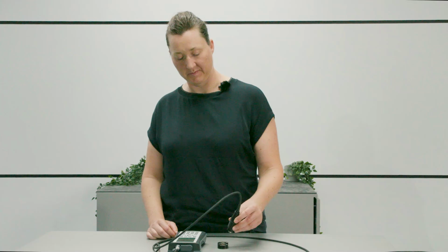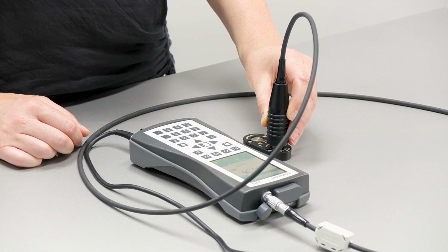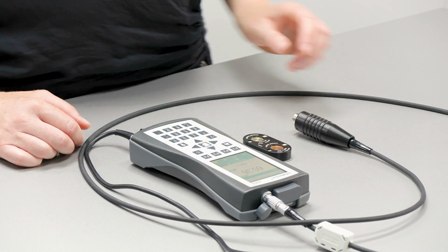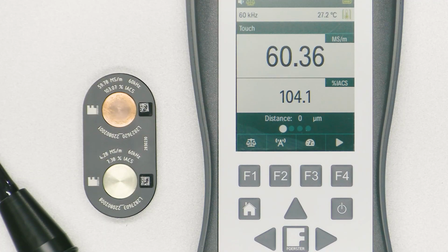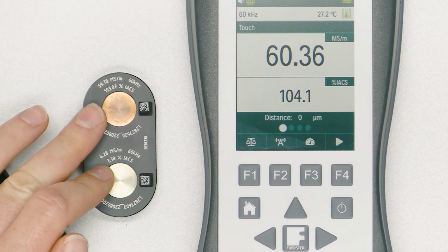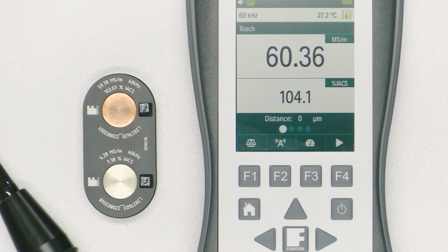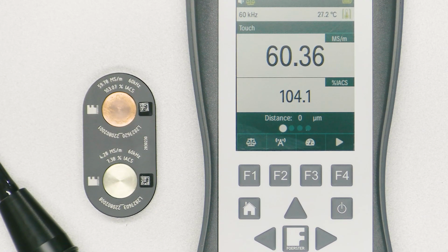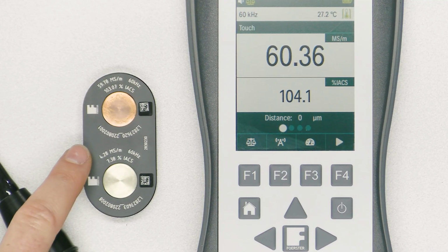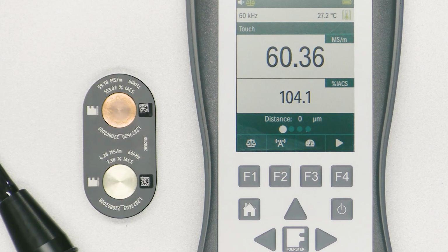Now I measure the first conductivity on the copper standard. If the measured value is not sufficiently accurate, the device must be adjusted to achieve the required accuracy. For the adjustment of the SIGMATEST, conductivity standards made of different materials are used. They are available as single, double, or triple standards. The standards are delivered with a certificate and are traceable to NPL standards. The respective conductivity is indicated on the plastic cover on the standard.